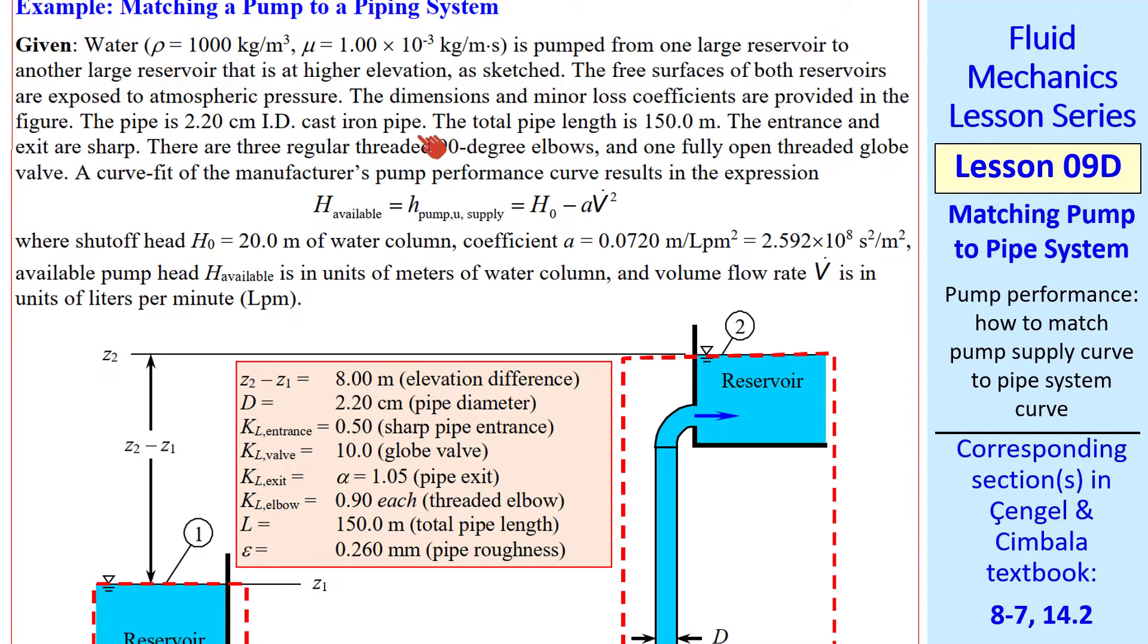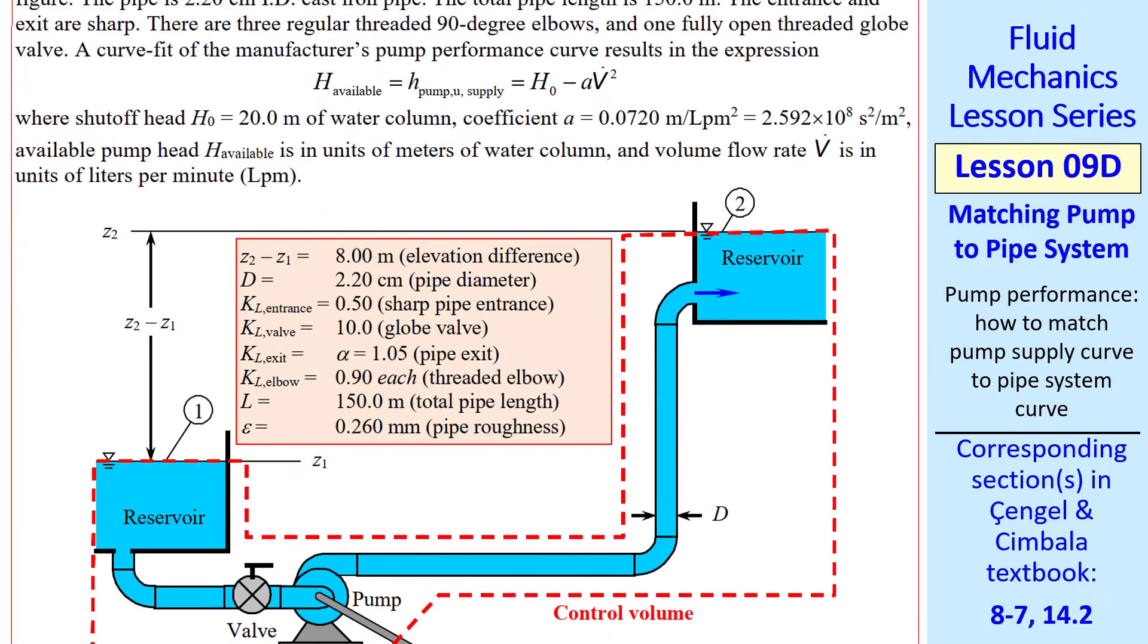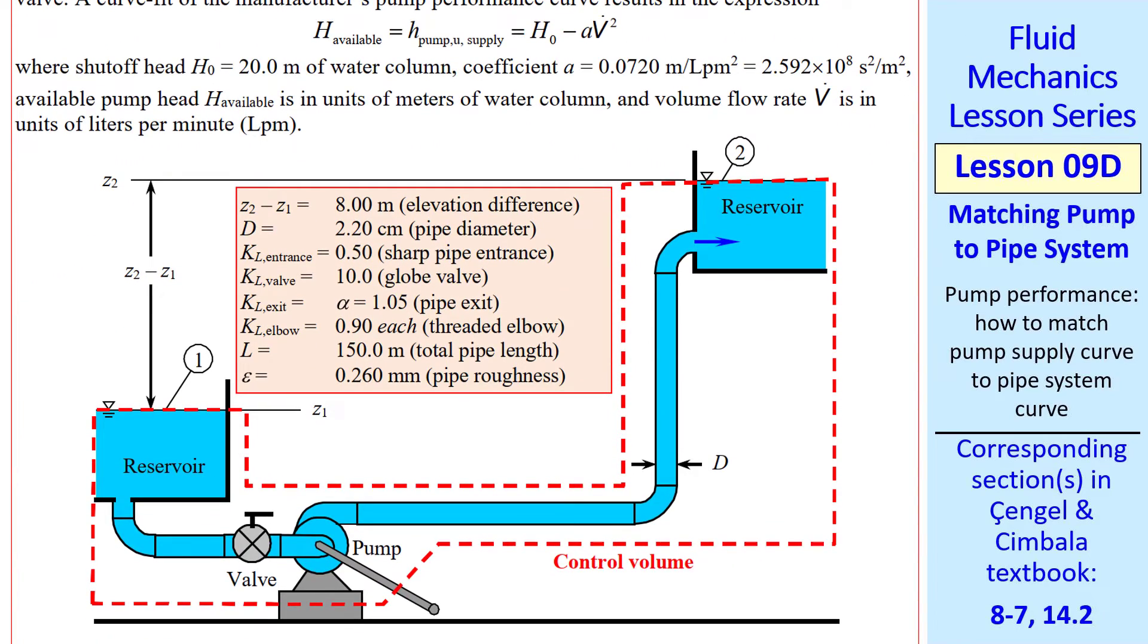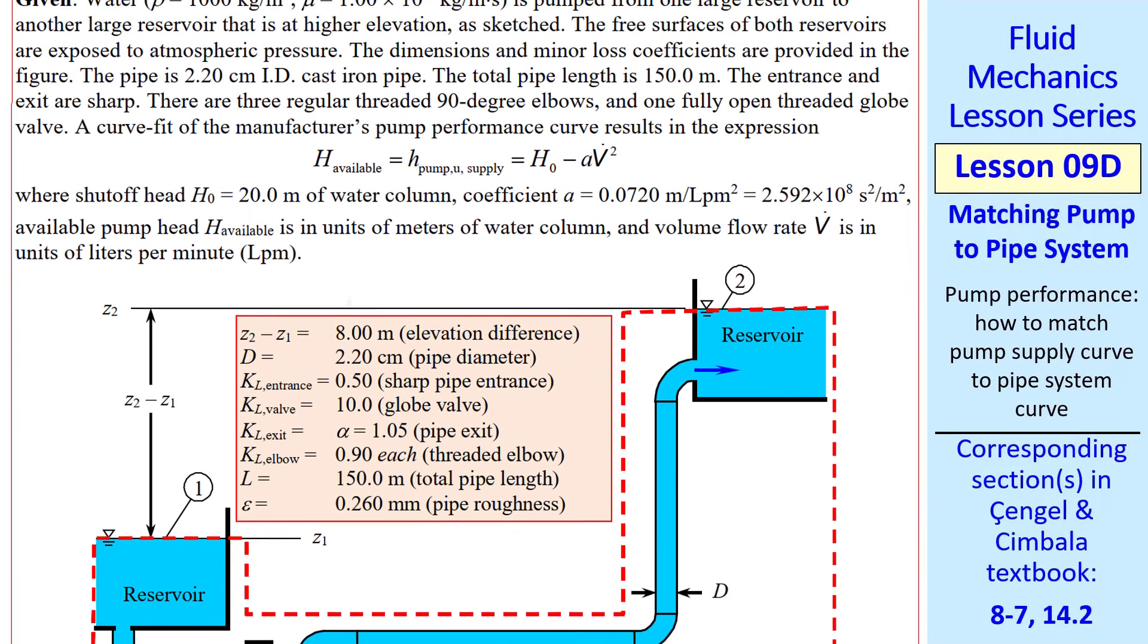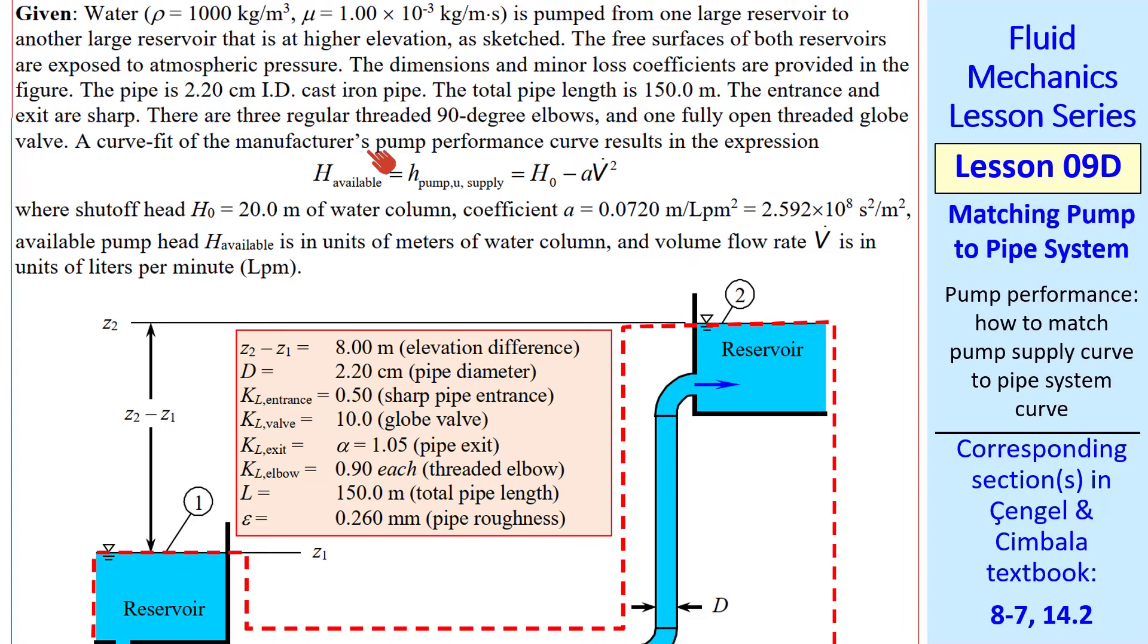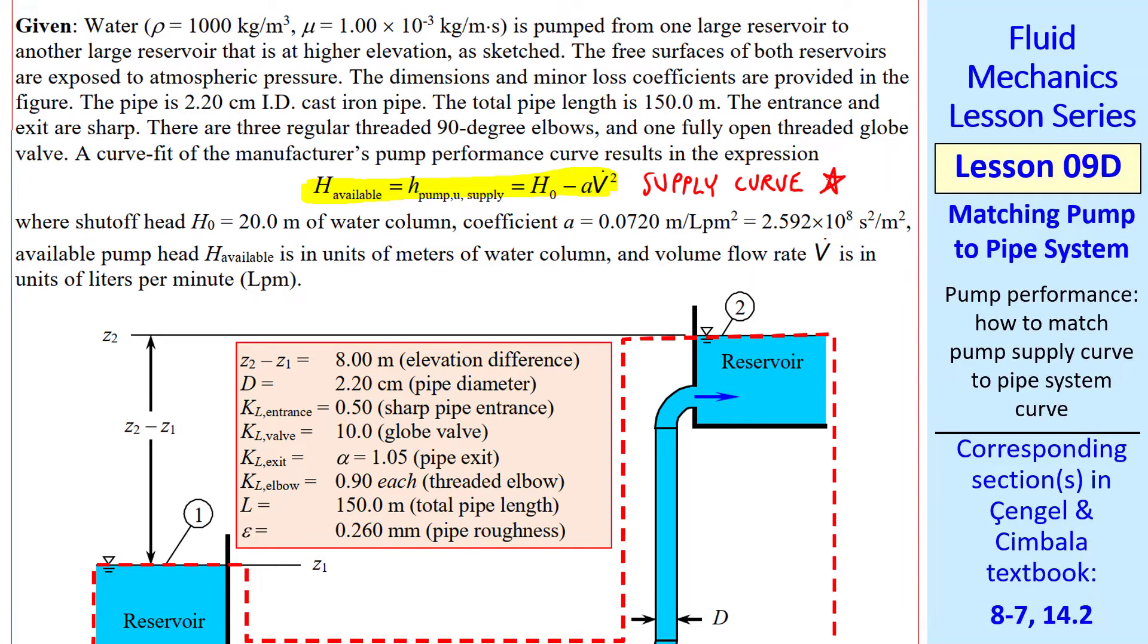We know how to generate the system curve. It's the same thing we've been doing for many example problems, except we'll do it not at just one volume flow rate but at several volume flow rates. We can create our system curve. What about the supply curve? Well that has to come from the manufacturer's pump performance curve specifications. What I did was a curve fit for this pump and created this equation. H available, or H pump U supply, is H0 minus A V dot squared. And these are the coefficients I obtained from the curve fit. So this equation is the supply curve.